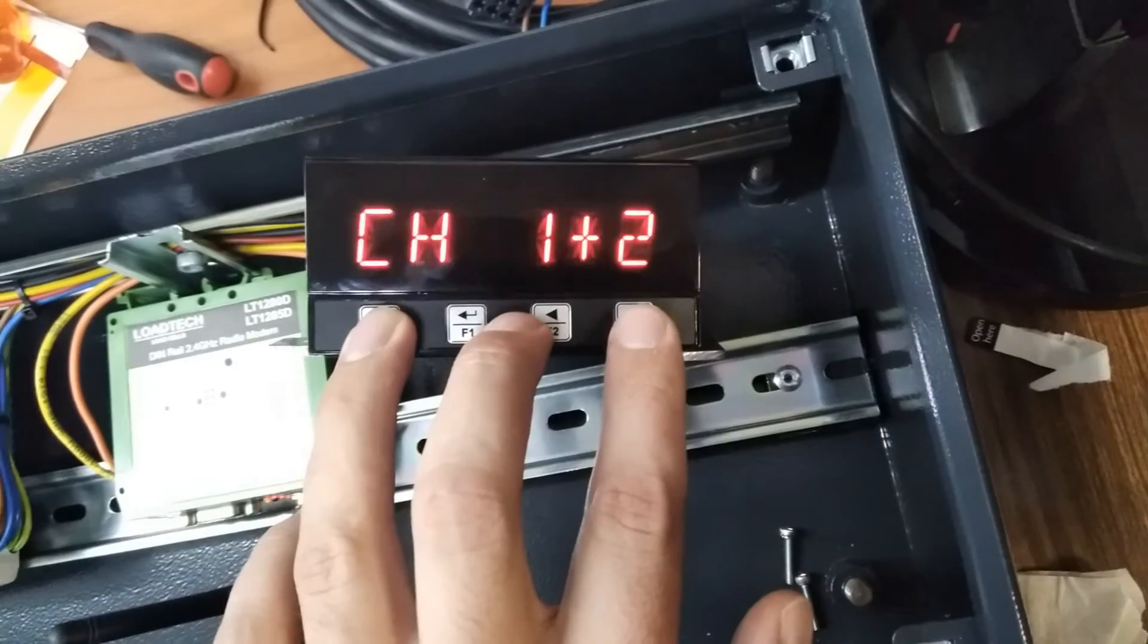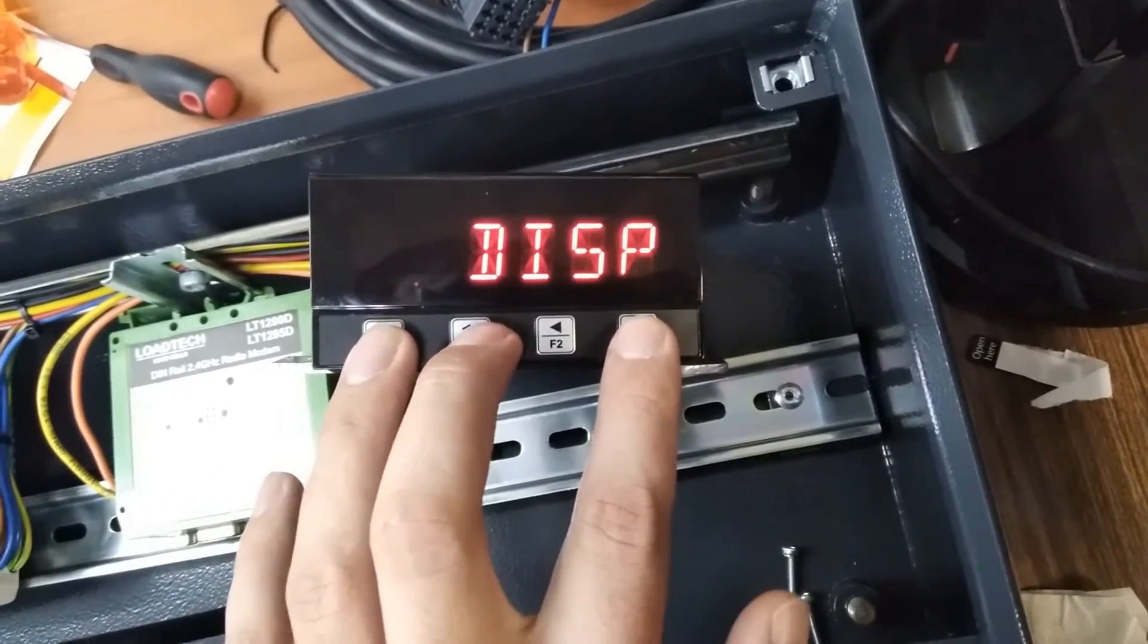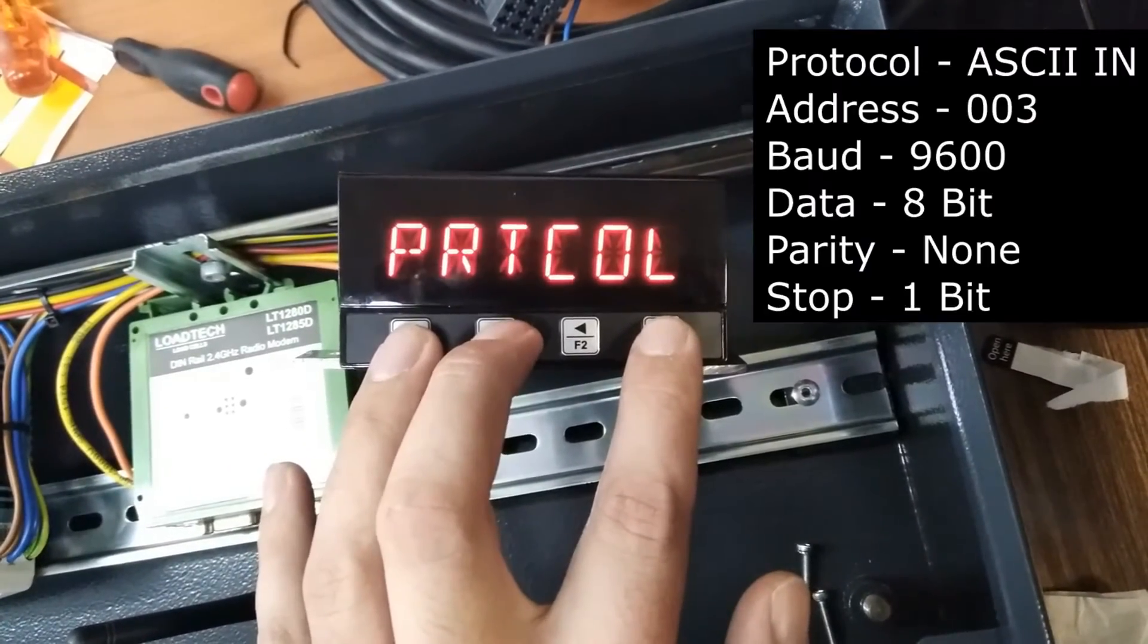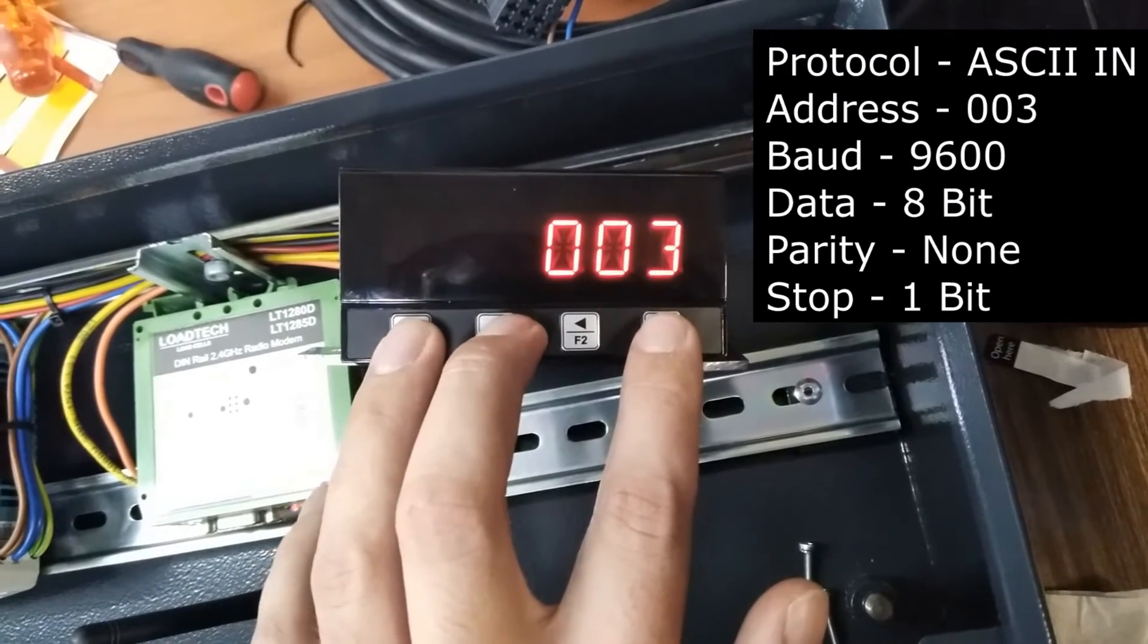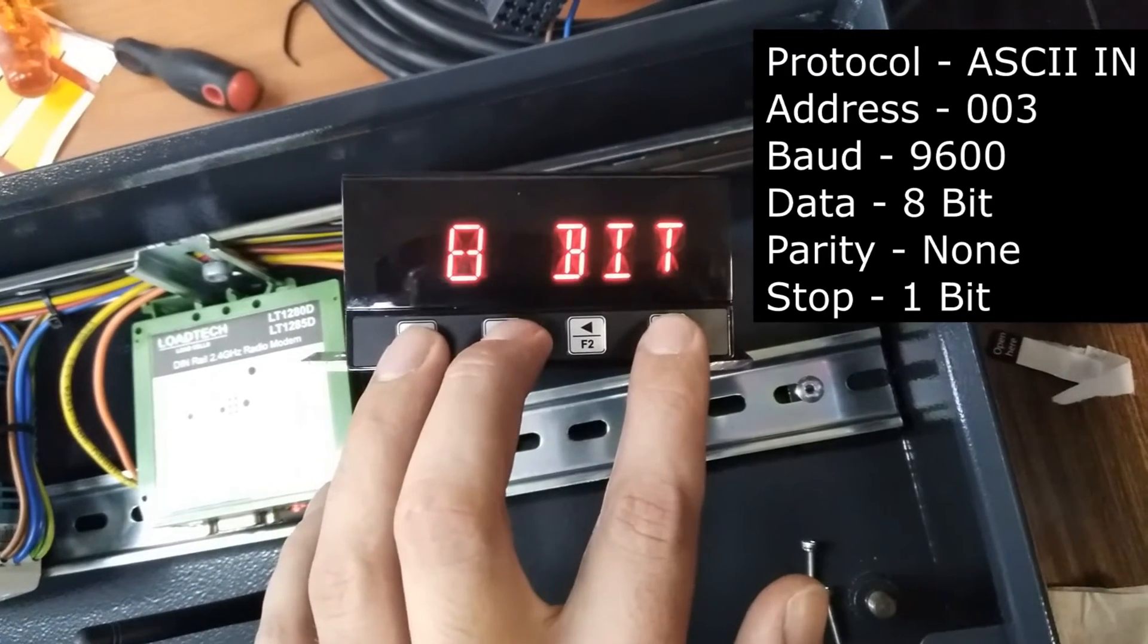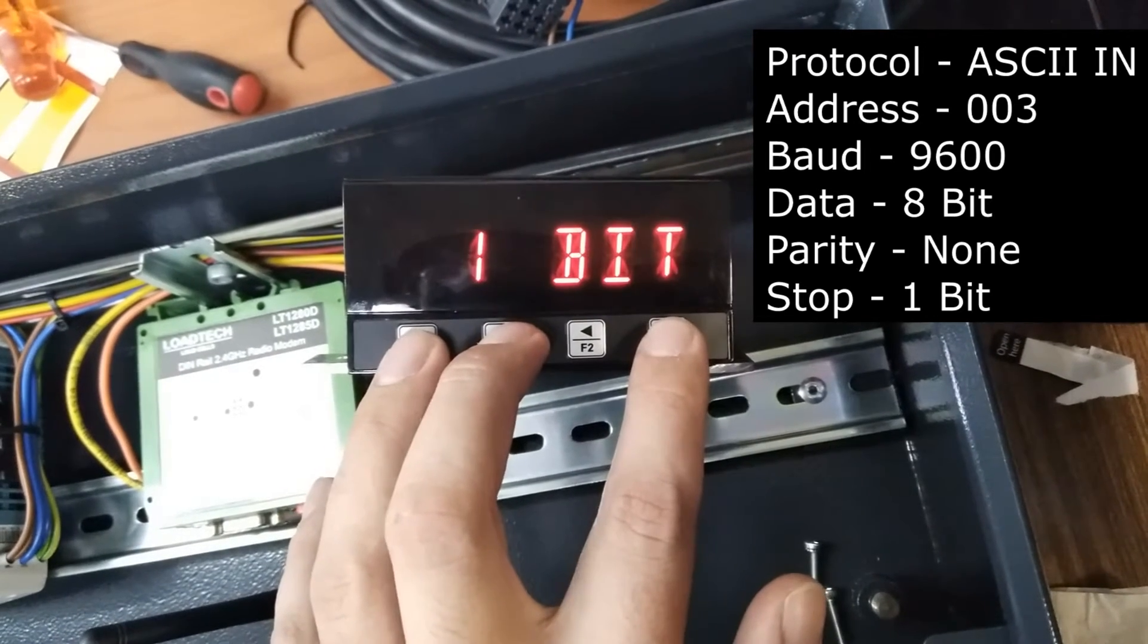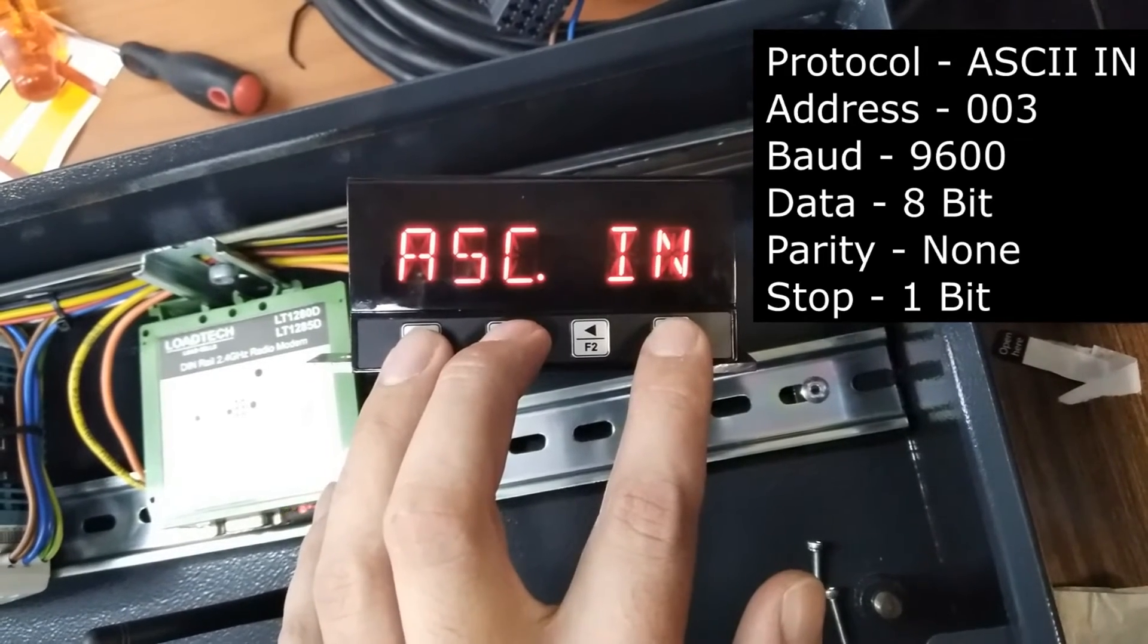Now looking at the 1230s, hold in your menu button. Navigate to RS-485. The settings will be on screen as follows. Protocol will be ASCII-IN. Address, 003. Baud rate, 9600. Data, 8-bit. Parity, none. Stop, 1-bit. Timeout can stay on 001. And that should be it.